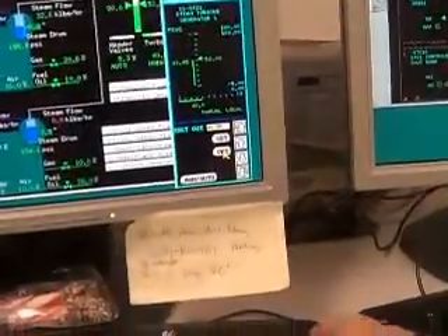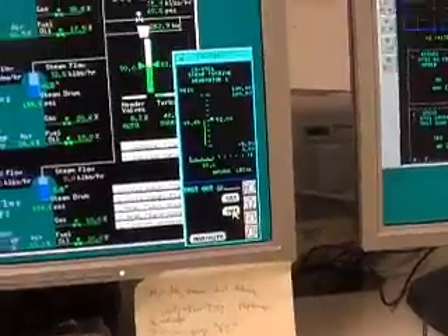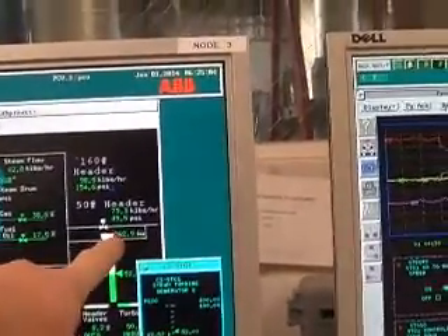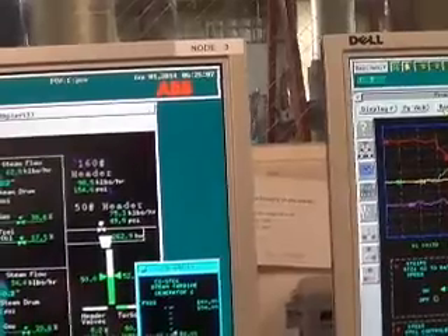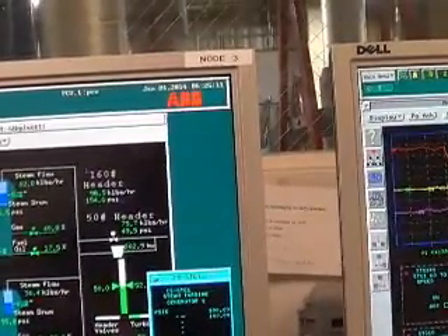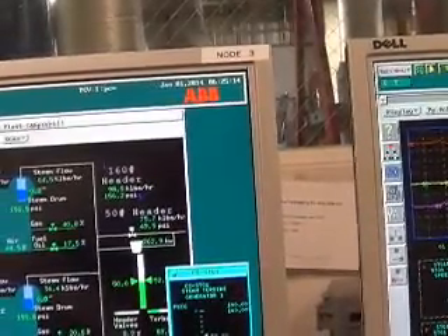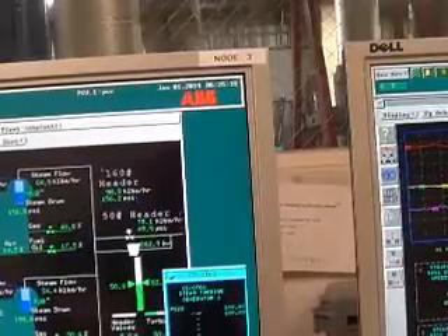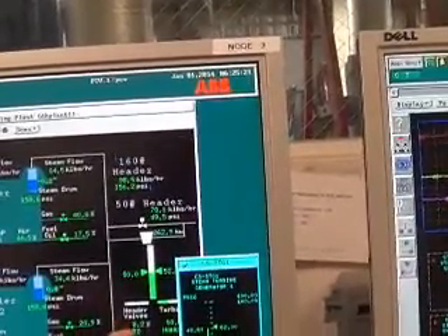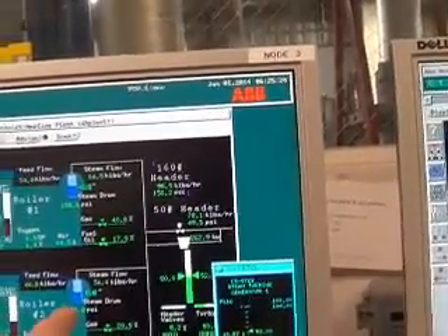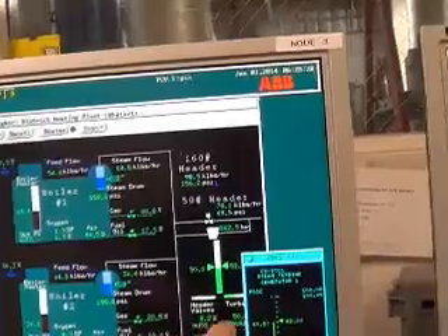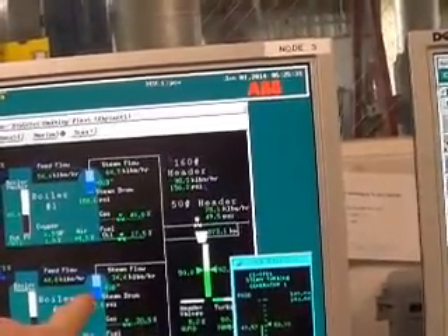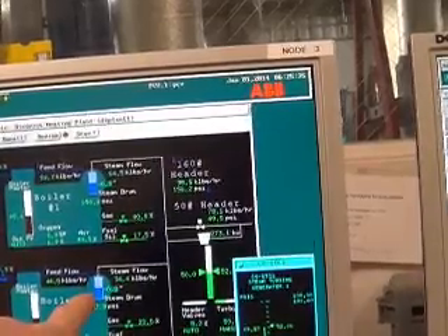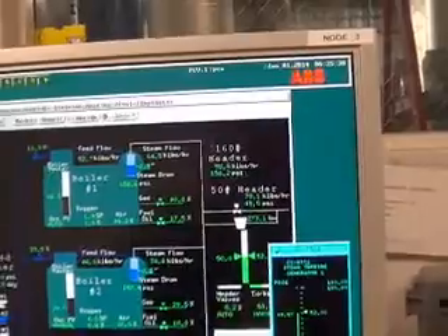Since my steam level is correct, I'm going to go ahead and raise it 10 pounds, go to 50, double check it on the screen, enter. Now we'll be making more electricity because we're going to be allowing more steam to go through the turbine. And the lift valve for the loop, you have two sources. If you're not going through the turbine, you're going through reducing stations, and we'll watch that back down, and we'll watch our drum level. Now when you let more steam out suddenly, the steam drum level increases a little bit. It went up, now it goes down. It doesn't vary very much.